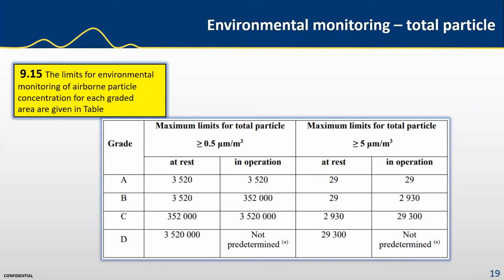So look at section 9.15. The limits for environmental monitoring of airborne particle concentration for each graded area are given in this table. This is one of the tables I spoke about earlier, and you can find this under environmental monitoring total particle. As we can see, the limits here for grade A, B, C, and D are outlined for at rest and in operation conditions for 0.5 microns and for 5 microns at a sample volume of a cubic meter. So we see that the 5 micron data in a grade A environment is based on a per cubic meter sample, and the limit is 29 particles for both at rest and in operation environments. For 0.5 microns, the concentration limit per cubic meter is 3,520 for both the at rest and in operation stages.